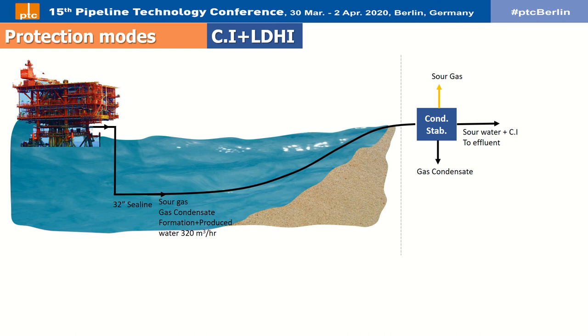The platform is equipped with a corrosion inhibitor package to provide protection when the pH stabilization technique is out of service. Injection rate is based on 20 ppm weight percent on total fluids. A well-suited inhibitor shall be effective in protecting surfaces across a wide range of operating conditions and diverse surface qualities. Fluid regime and velocity have the utmost effect on inhibitor efficiency, and although higher hydrodynamic parameters cause flow-accelerated corrosion, they lead to better inhibitor film persistence and distribution.